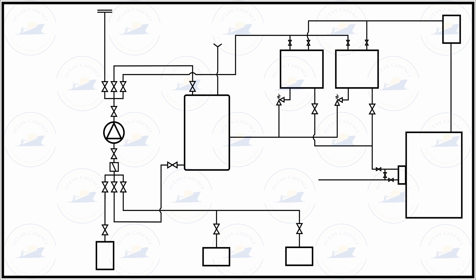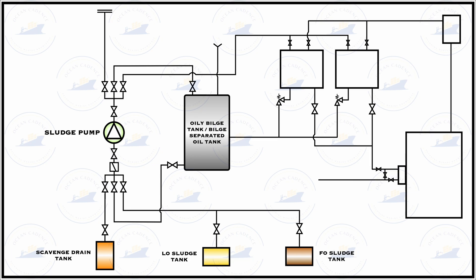In addition to understanding the sludge system, we will also understand how this is handled. As we can see on the line diagram, the sludge pump would predominantly take suction from a number of tanks. The tanks that exist in this system include the fuel oil sludge tank, the lube oil sludge tank, the scavenge drain tank, and the oily bilge tank — also regarded as the bilge separated oil tank, commonly known as the BSOT. The fuel oil sludge tank and lube oil sludge tank are dedicated for sludge generated from the purifiers — the fuel separator and lube oil separator — and usually contain a mixture high in water content due to intermittent discharge and water being separated from the fuel.